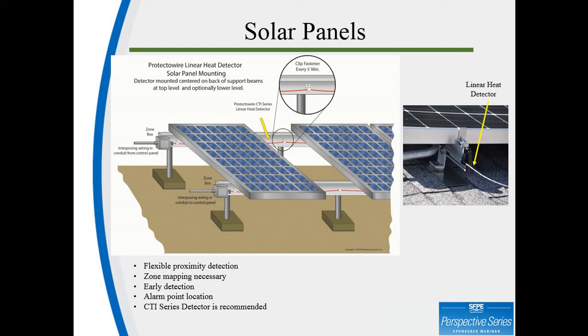Once more, for this application, we recommend the CTI series, and this is for two reasons. One, physical damage to the detector will not initiate a false alarm, it will only issue a trouble condition. And two, many of the solar panel installations are retrofit onto buildings that already have an existing fire alarm control panel. The CTM 530 interface module is a simple means of integrating linear heat detection into an active system.